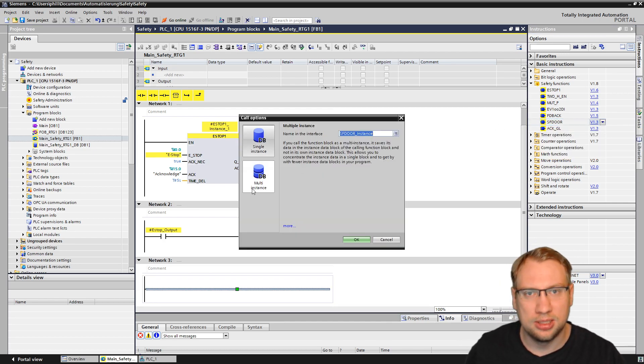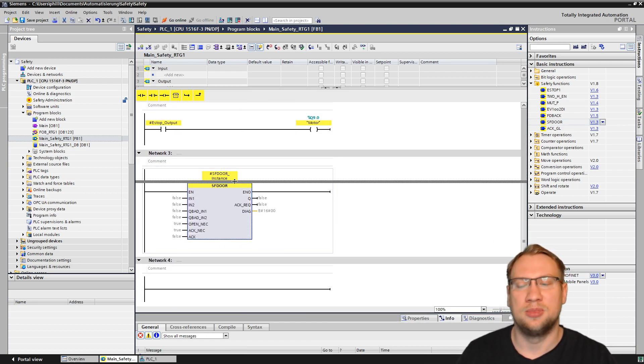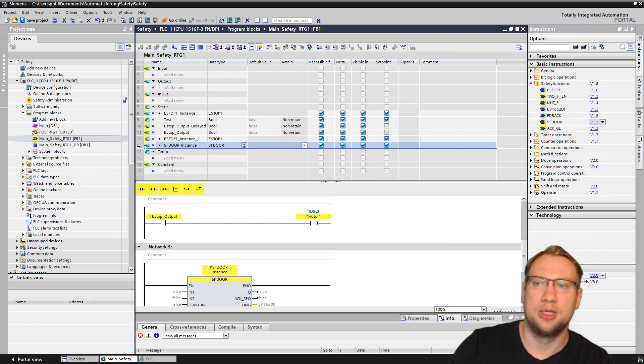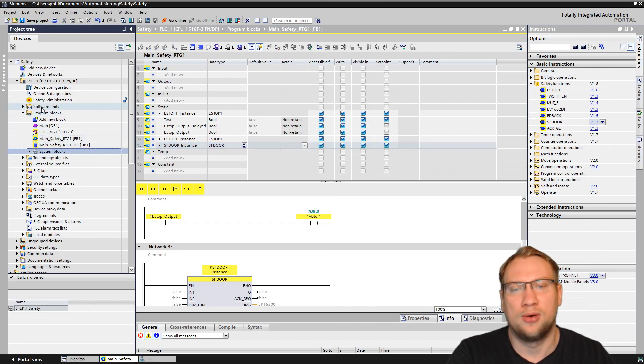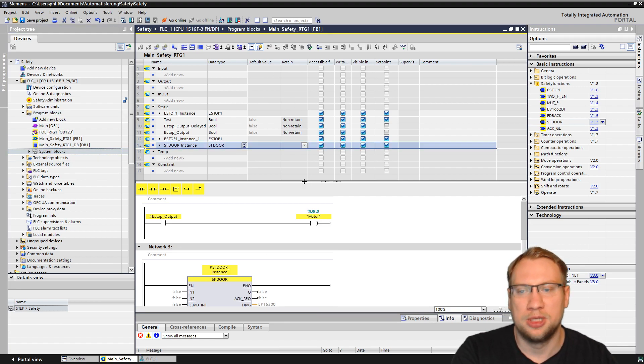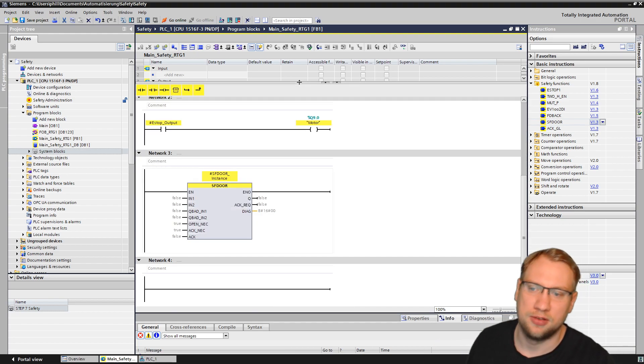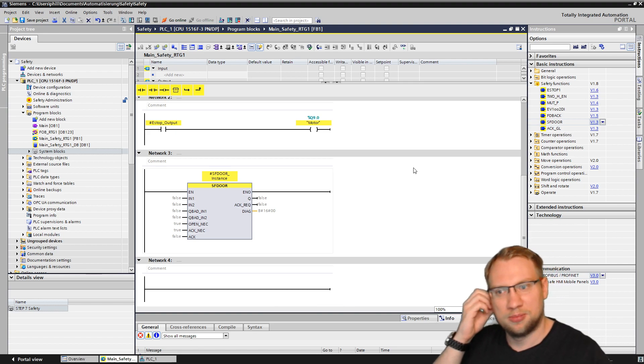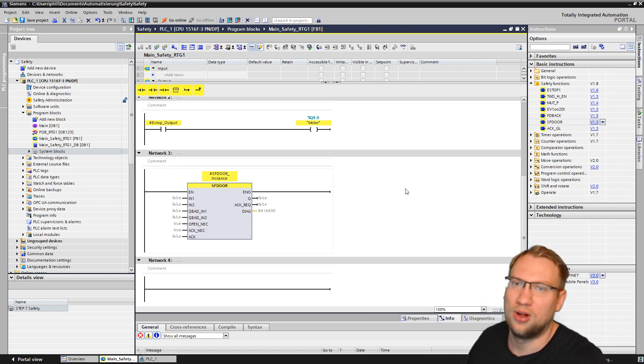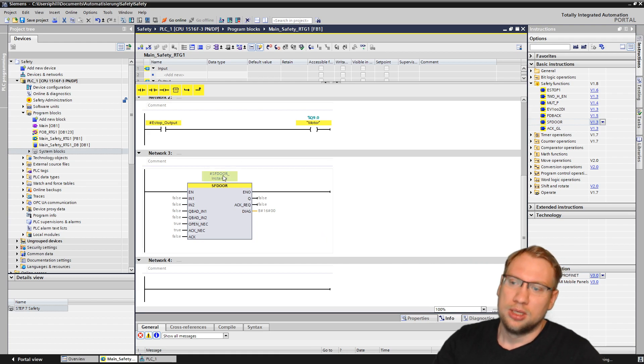I will make this a multi-instance. If we make it a multi-instance, we have the data block just in our parameters up here — we do not have an additional block in our program blocks list. We have this embedded in the main safety function, so it's an advantage to use multi-instance here: we don't have all the blocks scattered somewhere in our program where we don't need them.